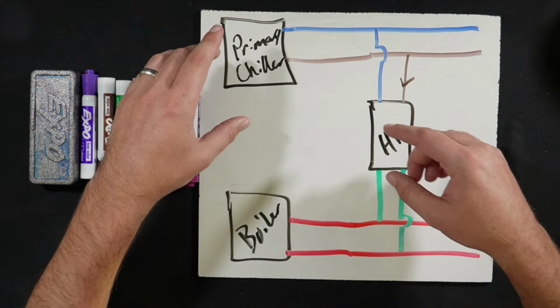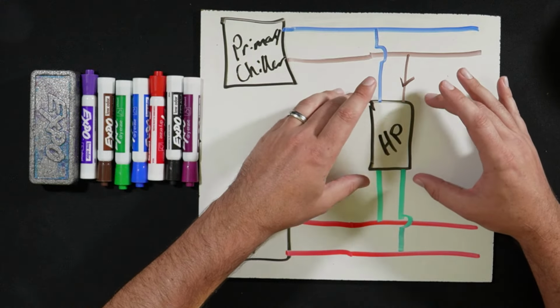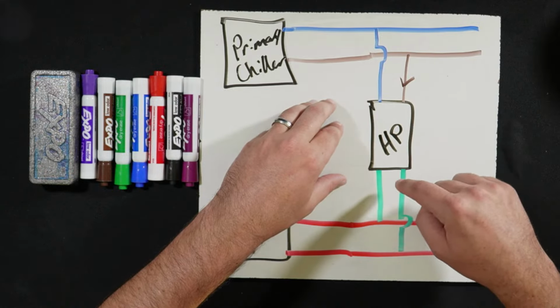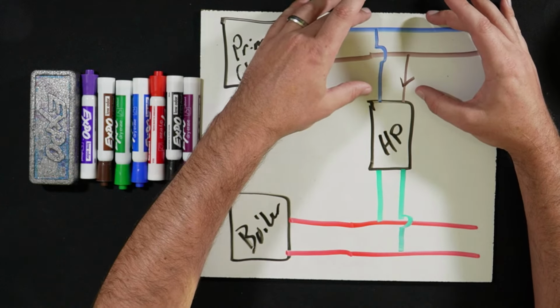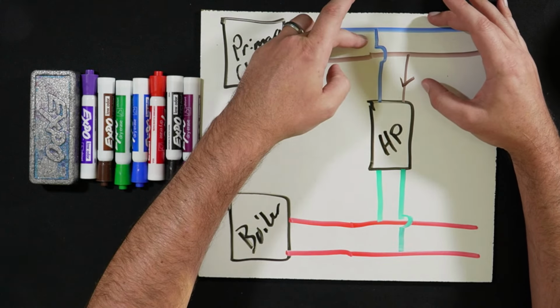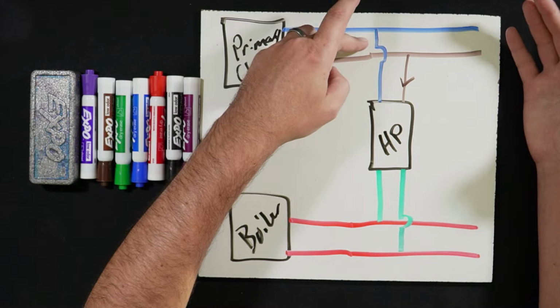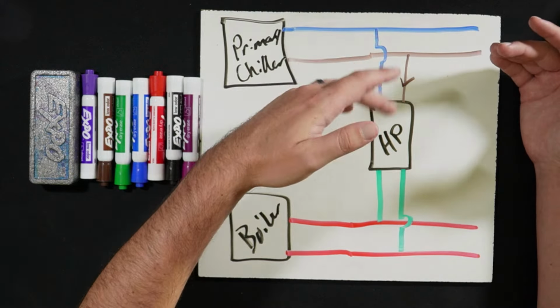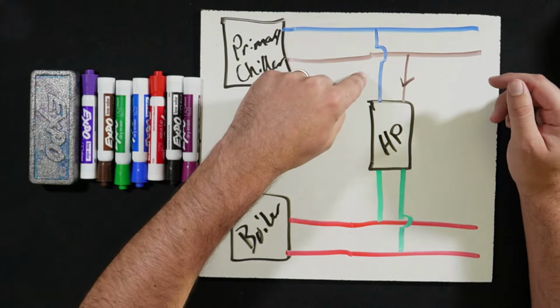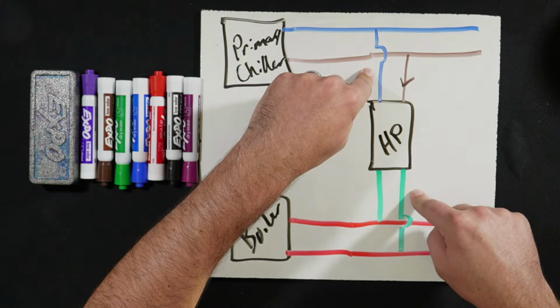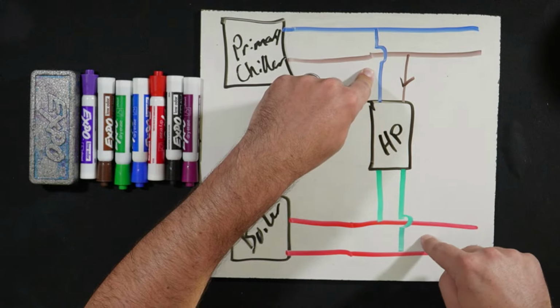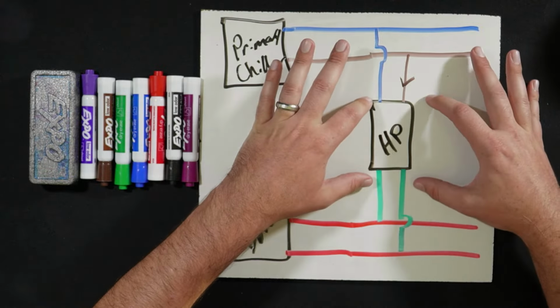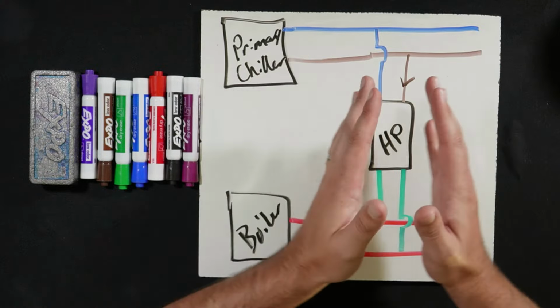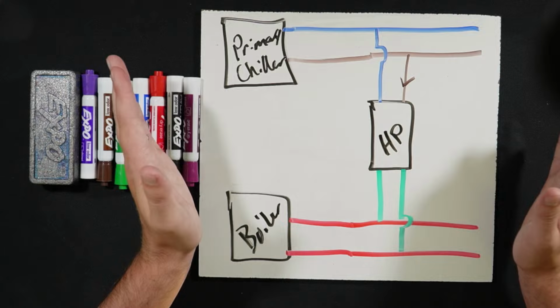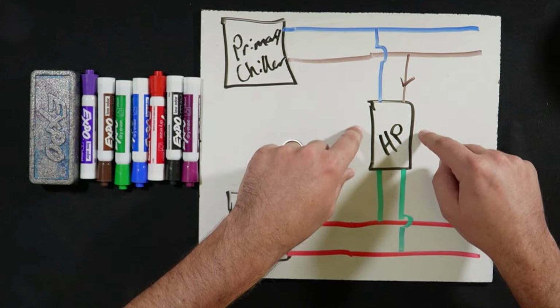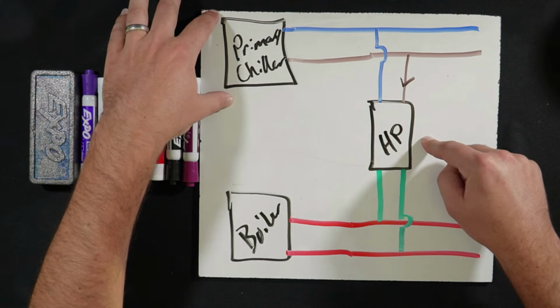And that's where these are designed to handle those hot water temperatures while also being able to manage the chilled water cooling, because we do still want to achieve a 45 degree leaving water here, or whatever the set point is the facility needs. We still want to achieve this, but we also want to be able to contribute actual hot water to a heating loop. And so it changes how we're going to design this, what the tonnages are. Our lift and our compression ratio is significantly higher by design on a system like this, in a completely different way than this would be.